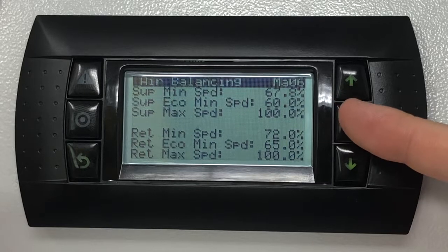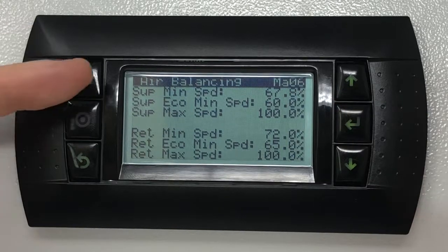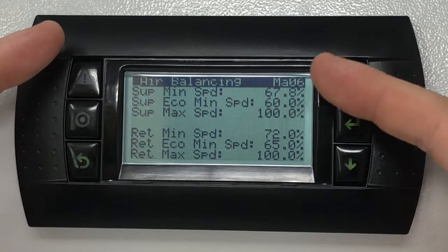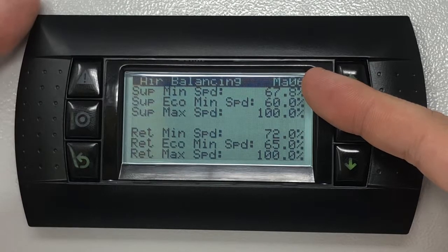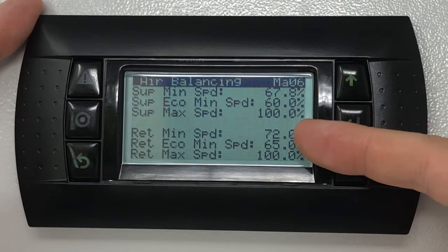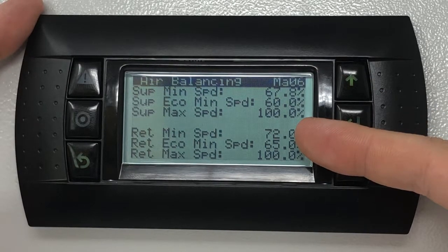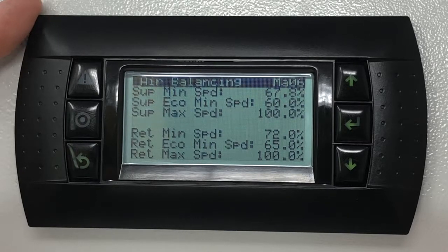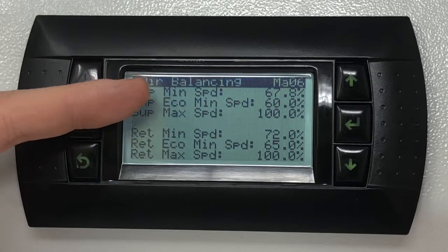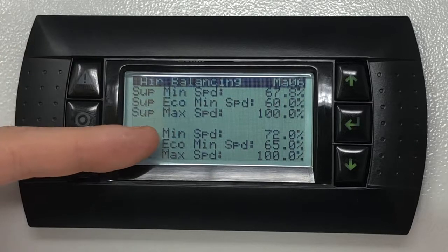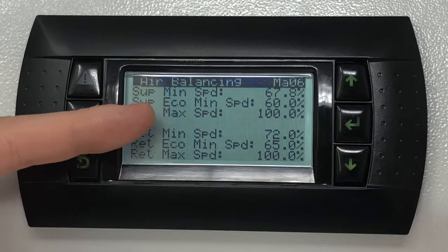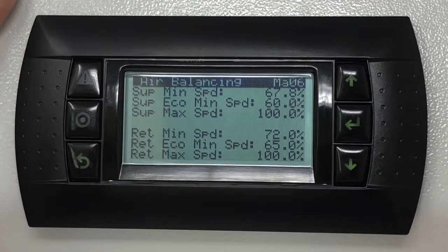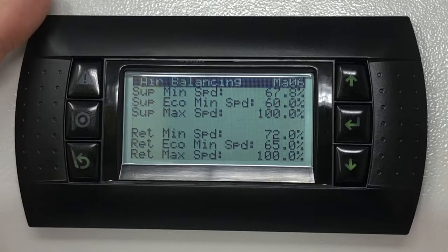The supply minimum speed settings refer to the lowest speed that the supply fan will be allowed to slow down to. The same applies to the return minimum speed settings. If the software has been set to operate both in comfort and economy modes, in this screen you will also be presented with a supply fan economy minimum speed setting. The same applies to units equipped with a return fan.